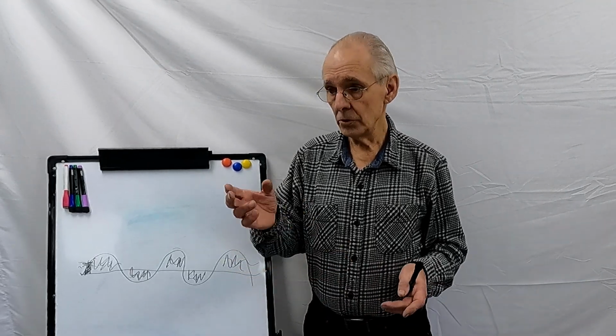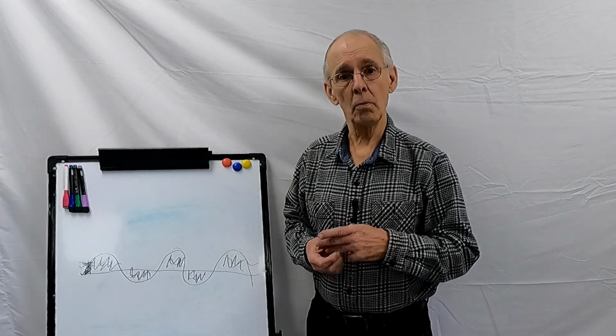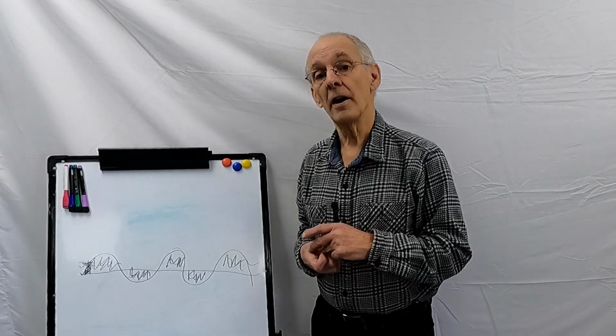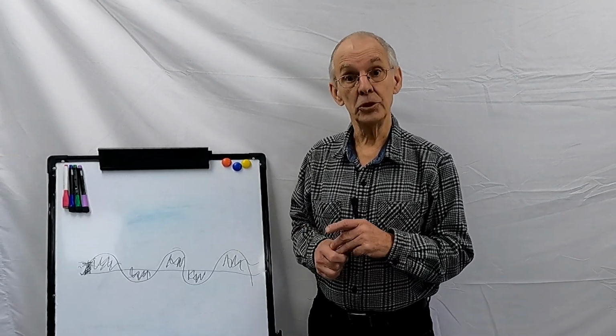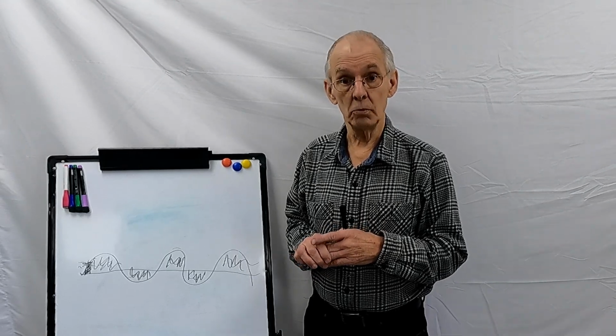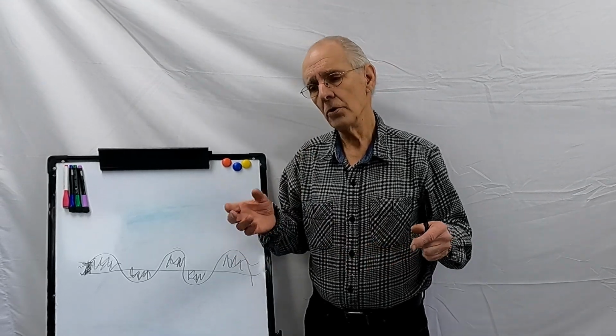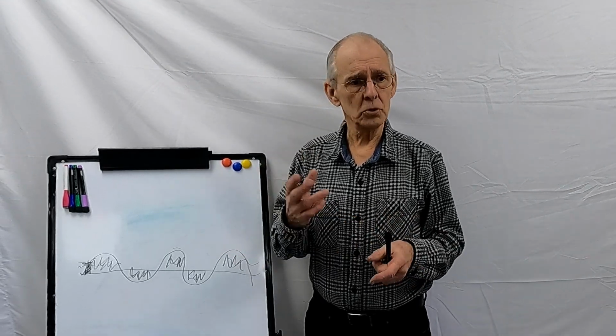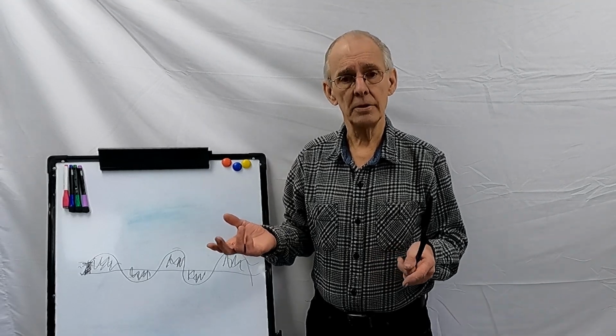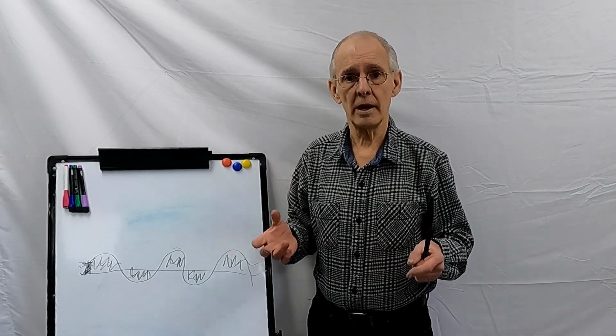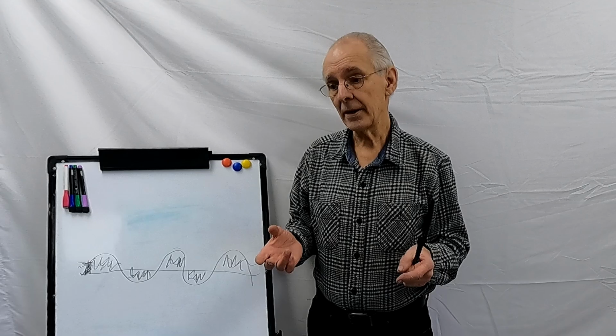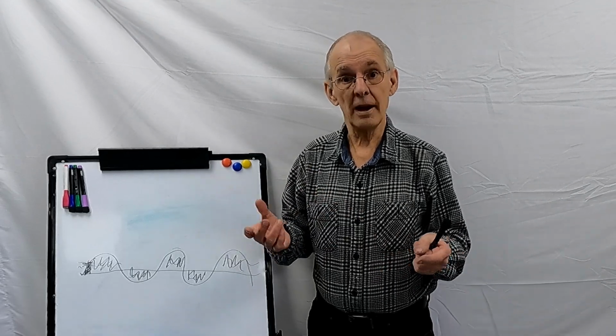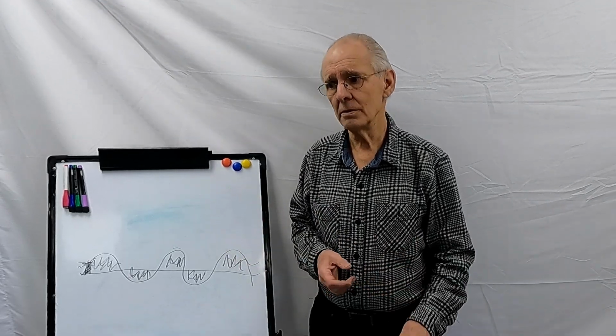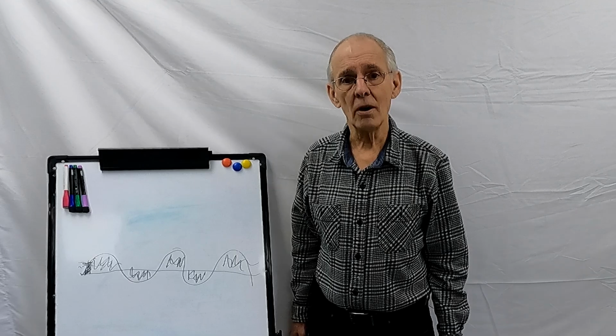So when we're doing this wiring in this little control panel, we need to go find the circuit breaker that feeds the machine and turn that off so that we're protected. Because you don't know, there could be a loose wire. A loose wire could pop out and strike ground and cause a hell of a bang. And that could be before the breaker or after the breaker. You just don't know, so the best thing to do is turn the power off.